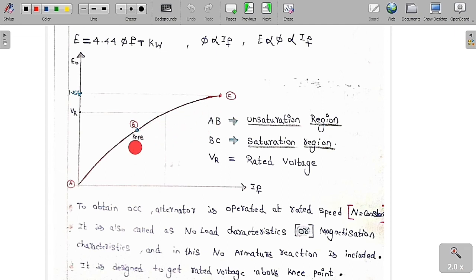So after B there is saturation, and before B there is no saturation, meaning the unsaturation region. Therefore you need more flux, more field current, to increase the EMF in this region because of the saturation effect. As IF increases, the flux becomes saturated, so the change in E is very small in the saturation region.